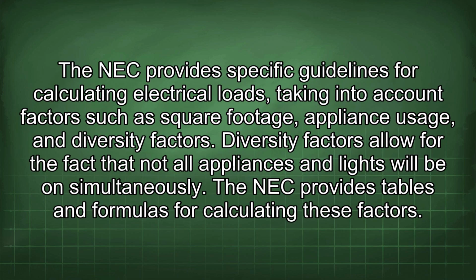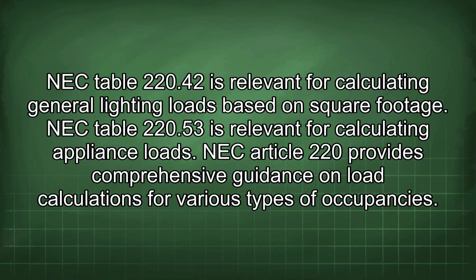The NEC provides specific guidelines for calculating electrical loads, taking into account factors such as square footage, appliance usage, and diversity factors. Diversity factors allow for the fact that not all appliances and lights will be on simultaneously. The NEC provides tables and formulas for calculating these factors. NEC Table 220.42 is relevant for calculating general lighting loads based on square footage. NEC Table 220.53 is relevant for calculating appliance loads. NEC Article 220 provides comprehensive guidance on load calculations for various types of occupancies.